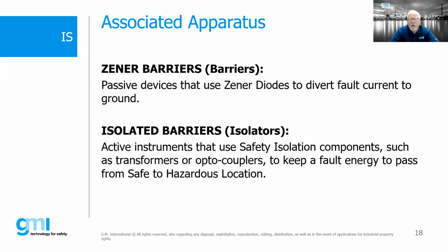Now, isolated barriers were a technology developed years later. They've been around for a long time now, but up until about 20 to 30 years ago, most barriers you'd find on the market were Zener barriers. Now we find many different manufacturers making isolated barriers or isolators. These are active components with safety isolation - typically a transformer or optocouplers to keep fault energy from passing from a safe to a hazardous location. So we're mimicking the signal from the control room out to the field device, using the protection of a transformer or optocoupler to keep a potential fault condition from traveling down that loop.